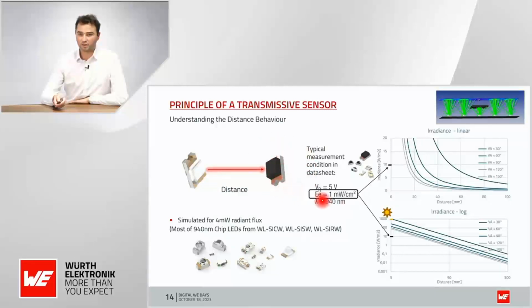on the detector. What I show you here is that sunlight is actually something like 1,000 watts per square meter of irradiance on a surface if you have direct sunlight. And this is like 2 orders of magnitude larger than what we typically have in laboratory environments. So you need to be really careful with sunlight, but more on this later.